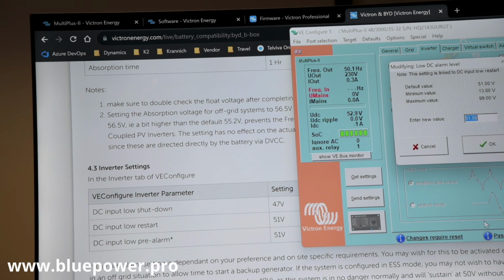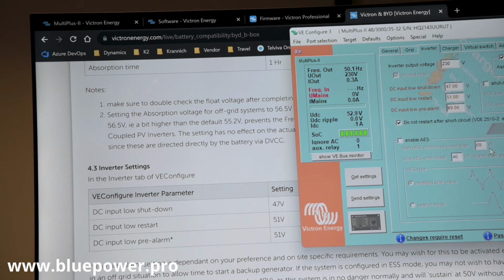So let's have a look at what BYD recommended over here. If the system is configured in ESS, you may not wish to have this alarm trigger until below the sustained voltage, e.g. 49 volts. Okay, so let's put that at 49 volts, because we're going to run an ESS Assistant.